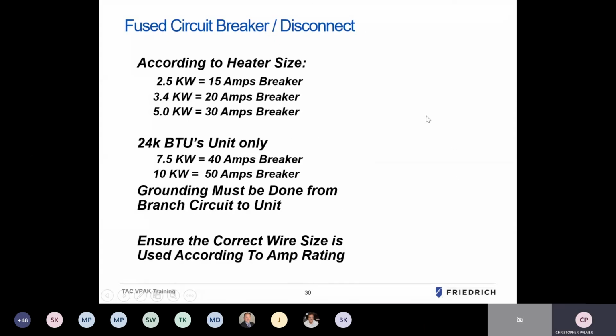Based on the fuse, circuit breaker, and disconnect size, we're looking at a 2.5 kilowatt versus a 15 amp breaker, 3.4 kilowatt versus a 20 amp breaker, 5.0 kilowatt versus a 30 amp breaker. And on the 24K units only, we have the options of a 7.5 kilowatt at a 40 amp breaker size and a whopping 10 kilowatt at a 50 amp breaker size. Note that all units must be grounded completely through from the branch circuit, and to make sure that the correct wiring size is used in accordance with the amp rating. In the event that you have to pull a new wire run to match the breaker size and the heater size, it's always recommended to do so.